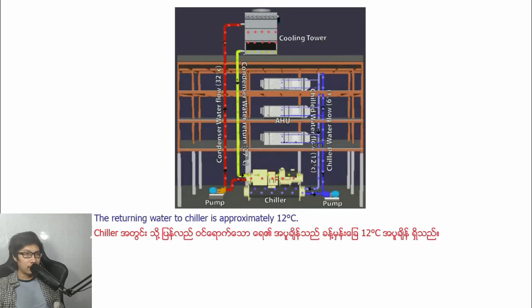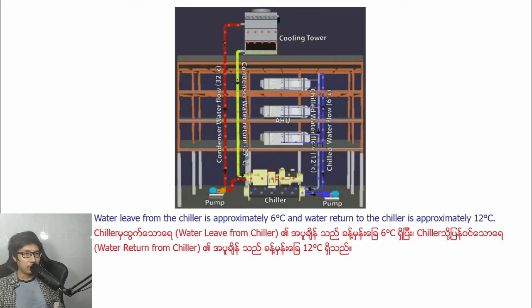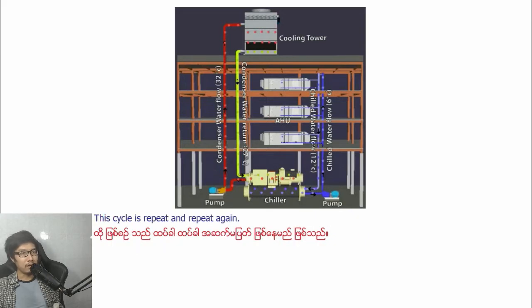This heat is then returned back to the chiller. The return water to the chiller is approximately 12 degrees Celsius. This water is then sent back through the chiller again. Water leaving the chiller is approximately 6 degrees Celsius and water returned to the chiller is approximately 12 degrees Celsius. This cycle repeats again and again.